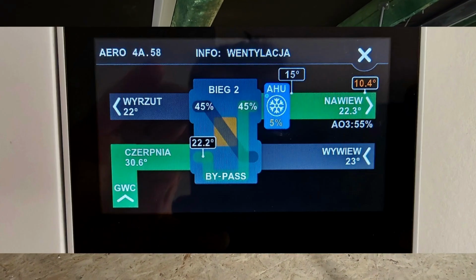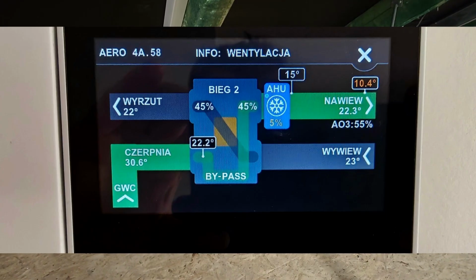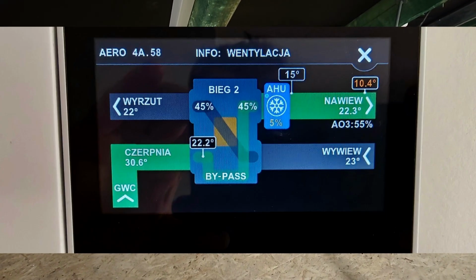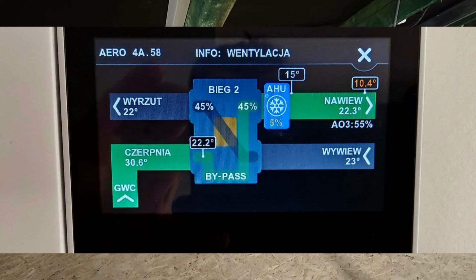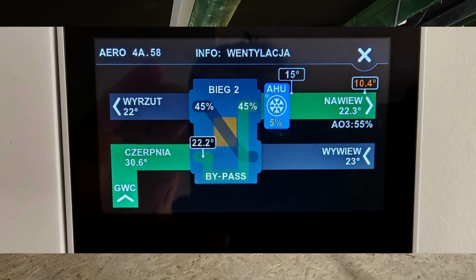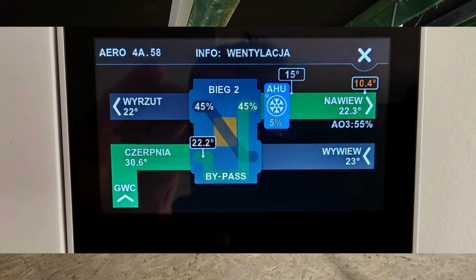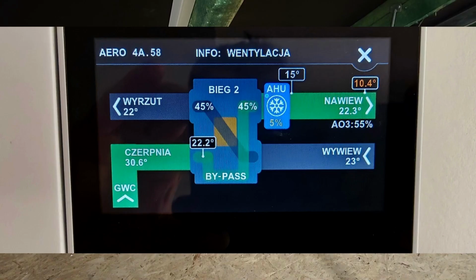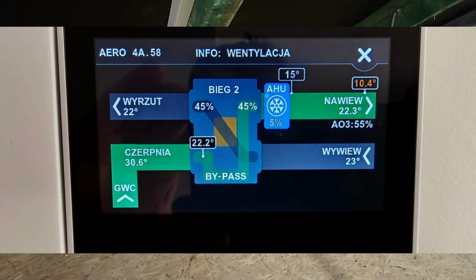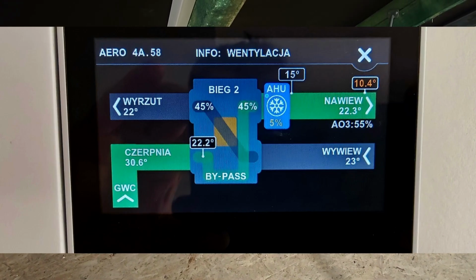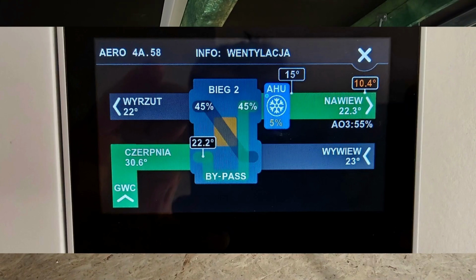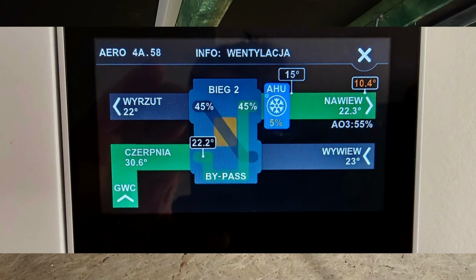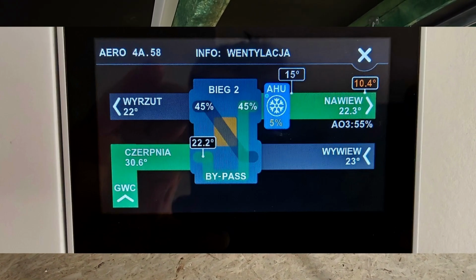According to my observations during the summer in hot weather, the temperature of the glycol coming from the ground, which is effectively the ground temperature, ranges from 16 to 18 degrees Celsius. With the nominal airflow for the building, this allows the air drawn by the recuperator to be cooled to around 21 or 22 degrees, even though its temperature before the exchanger often exceeded 30 degrees. For confirmation, I have some pictures of such moments.